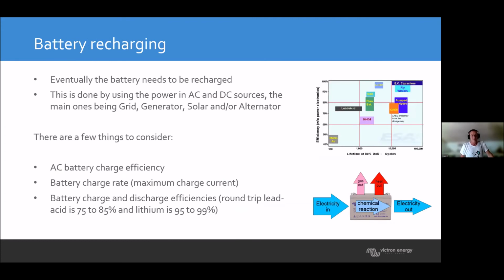Battery charging: we really need to see which kind of chemistry we're using when talking about charging, because if you're charging batteries with a genset - because there's no wind or no sun or whatever - it's too expensive to charge a lead-acid battery system, because of the absorption period. They start with around 85% of the battery capacity, and the amps go down because of internal resistance in the battery, so the genset will just be working at more or less idle, which is not quite good.